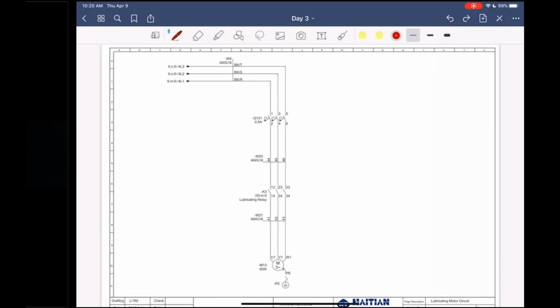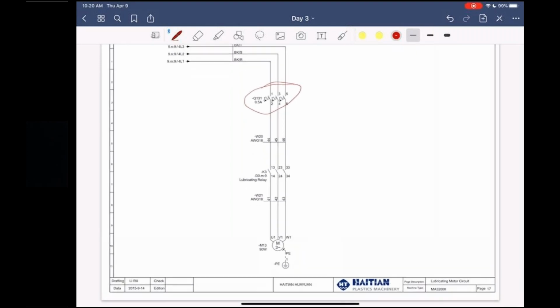This is the lubricating pump system. So we have Q131, which is a 0.5 amp breaker. Goes to W20, which is an 18 American wire gauge. And K3, which when it needs to lubricate, K3 will then send a signal to the relay, and that'll close the contacts, and the pump will run to supply lubrication to all the clamp end of the machine.